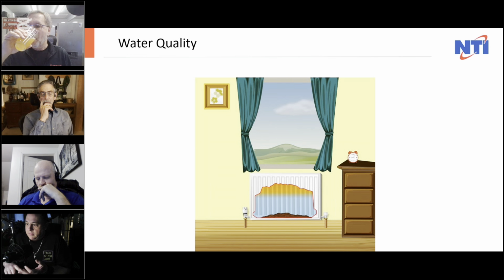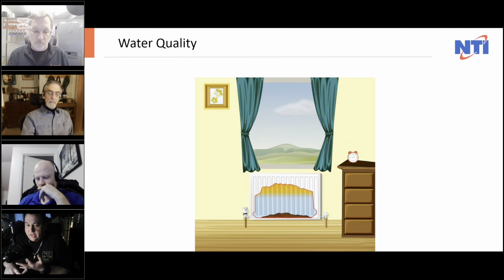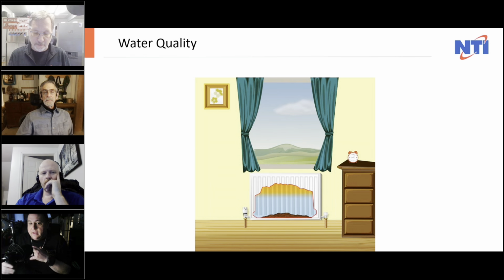How many of these boilers have you taken out? The old cast iron boilers are great filters because they held all that crap. They didn't have to worry about these big passages. So it's not just the boiler itself, but the overall system. Because remember, we don't just sell boilers, we sell systems now. We're adapting different types of technology, air to water, radiant, and you're bringing chillers in. There are a lot of different types of applications, and this is very important. Go back to that water quality on chillers and anything dealing with water, air to water.